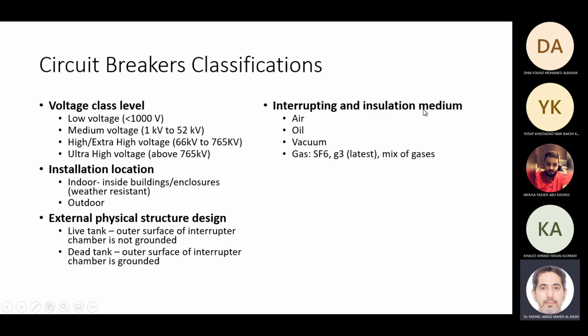Breakers are also classified based on the insulation and interrupting medium. If air is the medium, we call it an air circuit breaker. For oil, we call it an oil circuit breaker. Vacuum, we call it a vacuum circuit breaker. And gas, we can use SF6 or g3, which is one of the latest gases, or a mix of gases. They call it a gas circuit breaker.